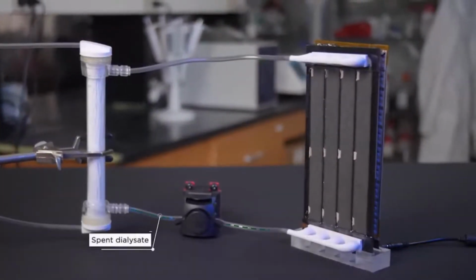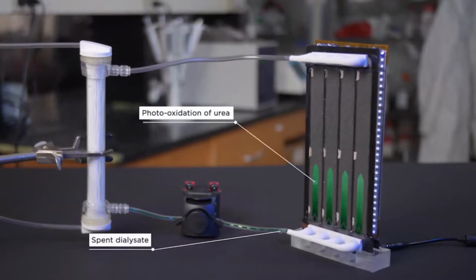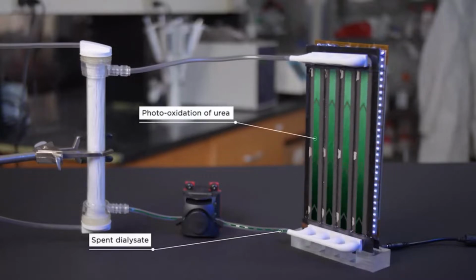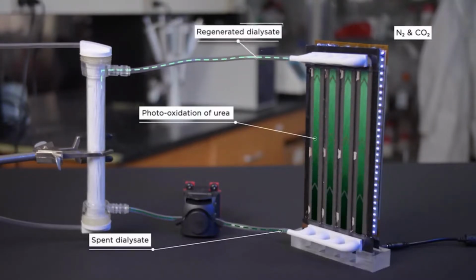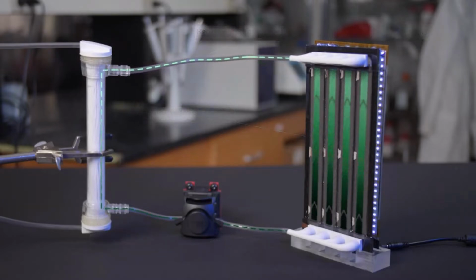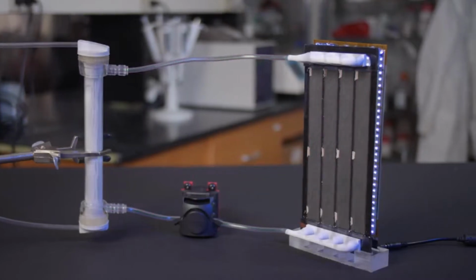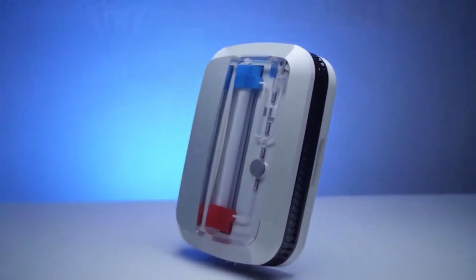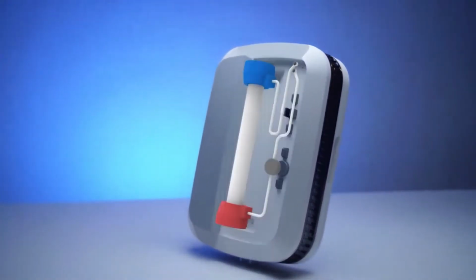Spent dialysate flows from the dialyzer to the dialysate regeneration module, where urea is decomposed into nitrogen and carbon dioxide by photooxidation. Regenerated dialysate is returned to the dialyzer, and this process repeats. The dialysate regeneration module untethers the Active from an external water supply and enables it to operate with a small, closed-loop volume of dialysate. This revolutionary technology allows the Active device to be smaller, lighter, safe, and effective for renal replacement therapy.